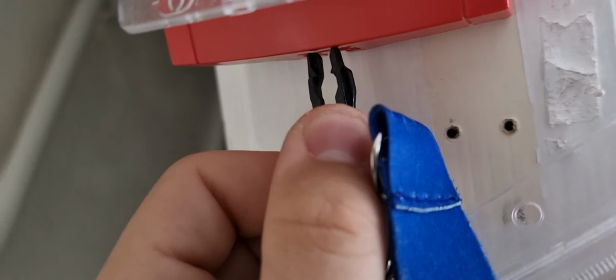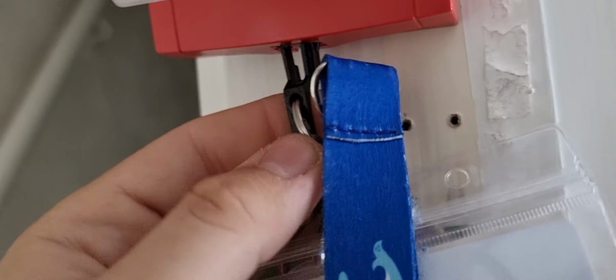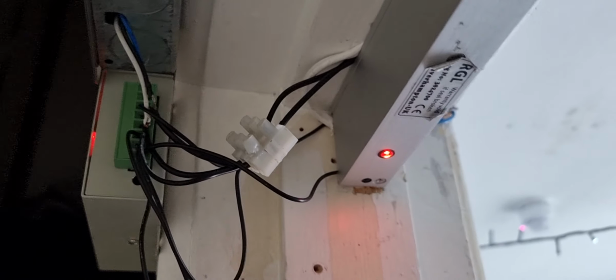And then my keys. So I'll just use these, but it's kind of a pain. Sometimes my door closer makes that noise, but it didn't this time, so I don't know. So what I do is I reset the call point. Sometimes it doesn't. So if you listen, the maglock and the power supply go off together, and then they come back on.